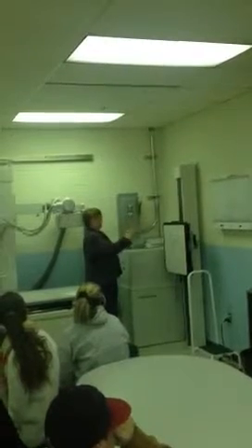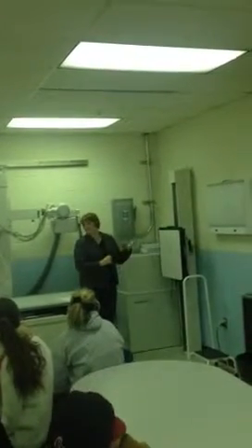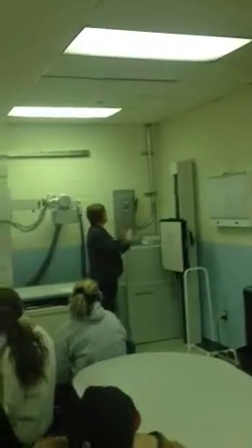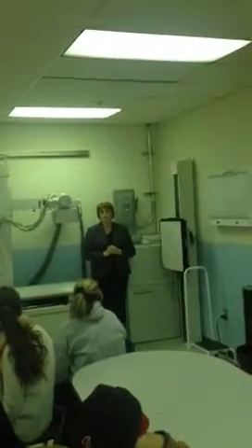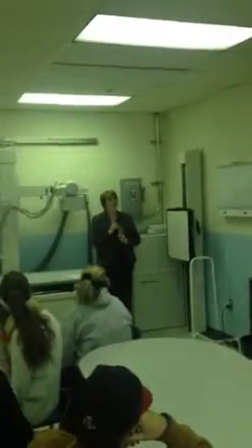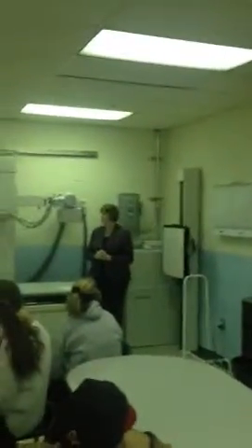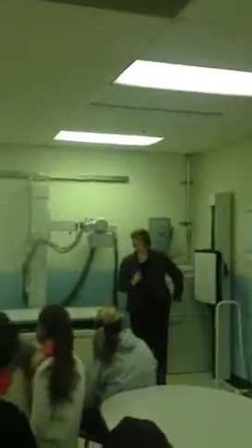So this is a primary what? Wall barrier. Yeah, primary barrier. How much lead is required to be in this wall? The use factor is 1. Very good. But what about the amount of lead? 1/16 inch, or millimeters? 1.6 millimeters. And how far from the floor upward must it go? 7 feet upward from the floor.